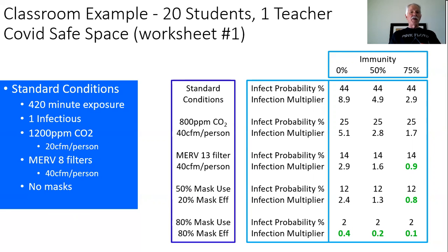We've gone from a level of about 20 cubic feet per minute per person to about 40 cubic feet per minute per person. That may sound outrageous, that may sound undoable to many of you, or if you're watching the energy budget, that you are picturing this as being excessive amount of air being brought in when you've been told operating at 1,200 parts per million is adequate to meet standard ventilation.